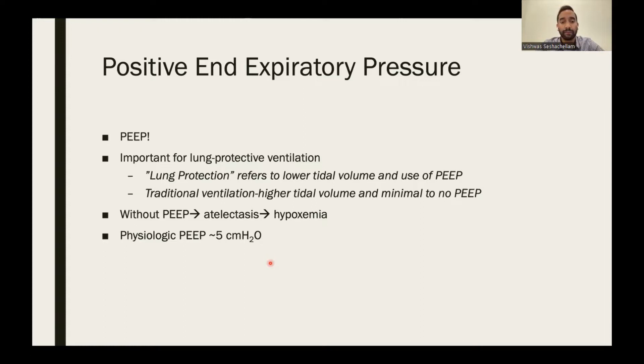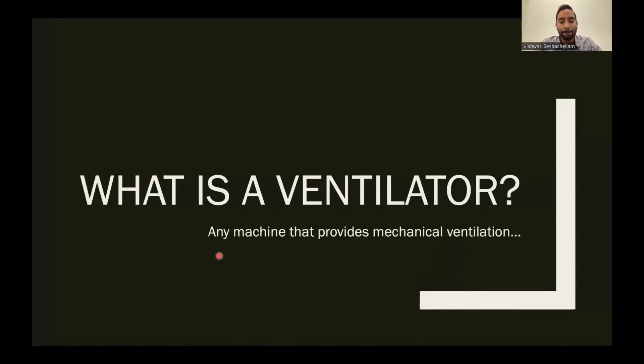So what is a ventilator? It's any machine that provides mechanical ventilation. My question to you is, does this have to be electronic? Does it have to have an electricity source? It does not. This is the simplest ventilator and a lifesaver. This is bag mask ventilation, hand ventilation. Before I go any further, every patient that has impending respiratory failure or is on the ventilator should have an ambu bag at bedside.